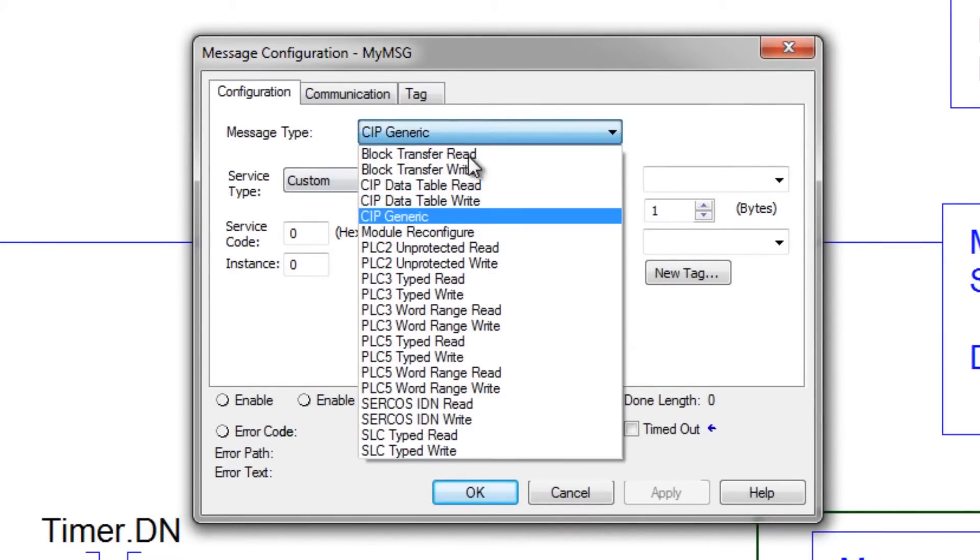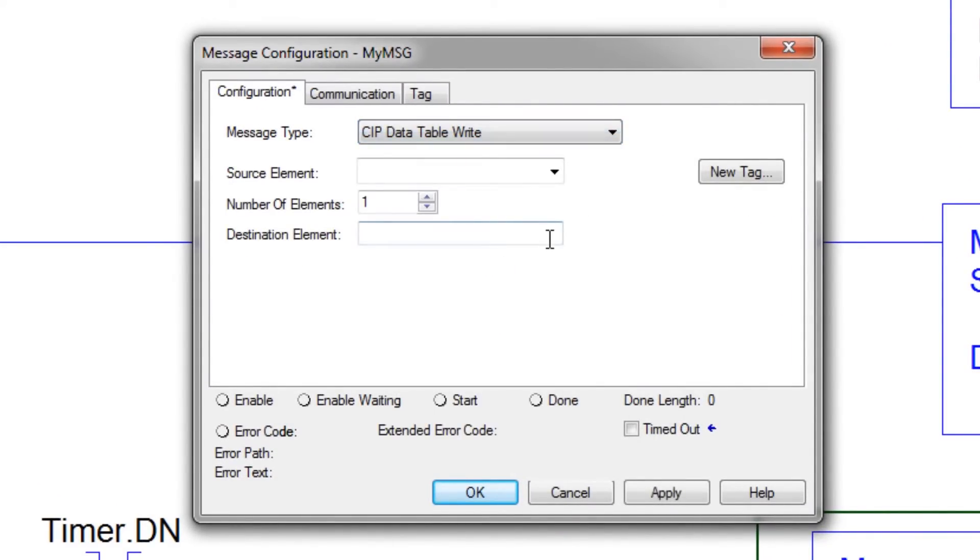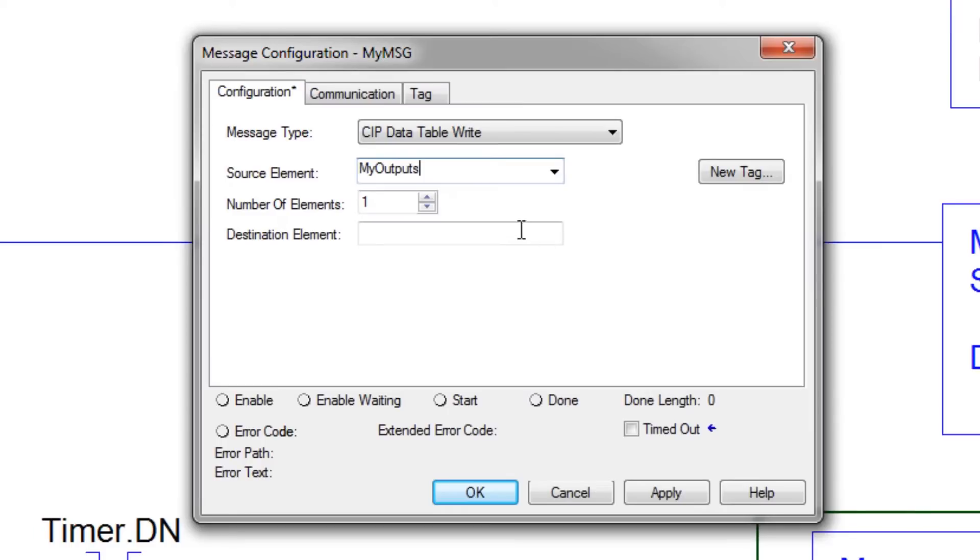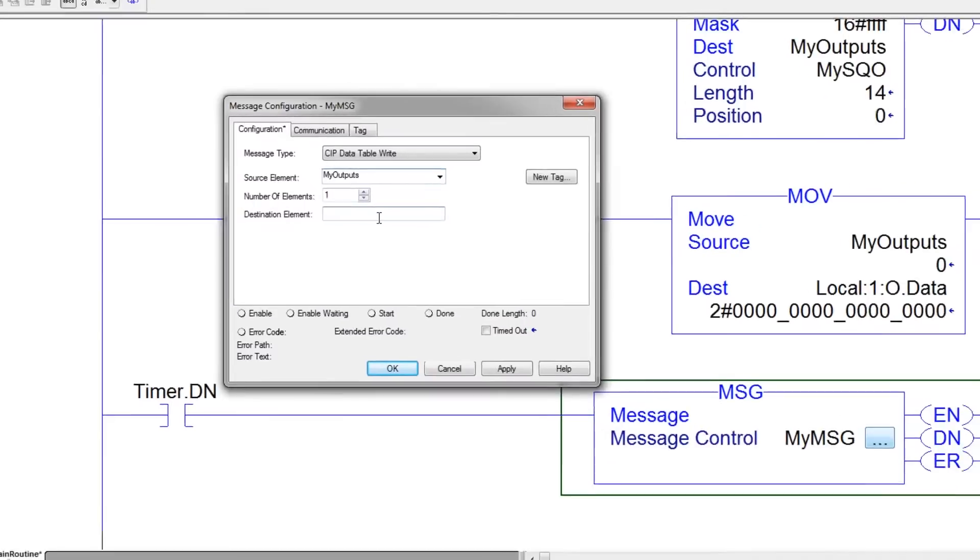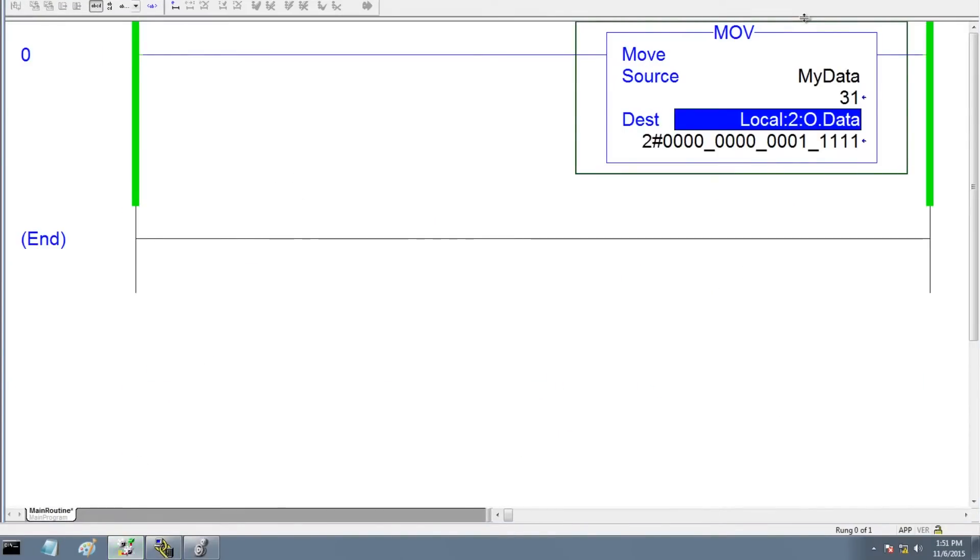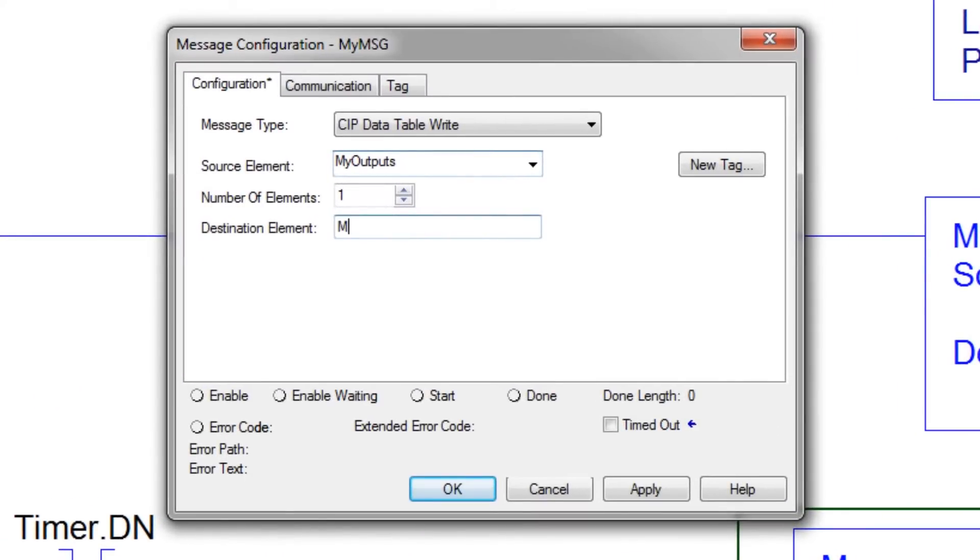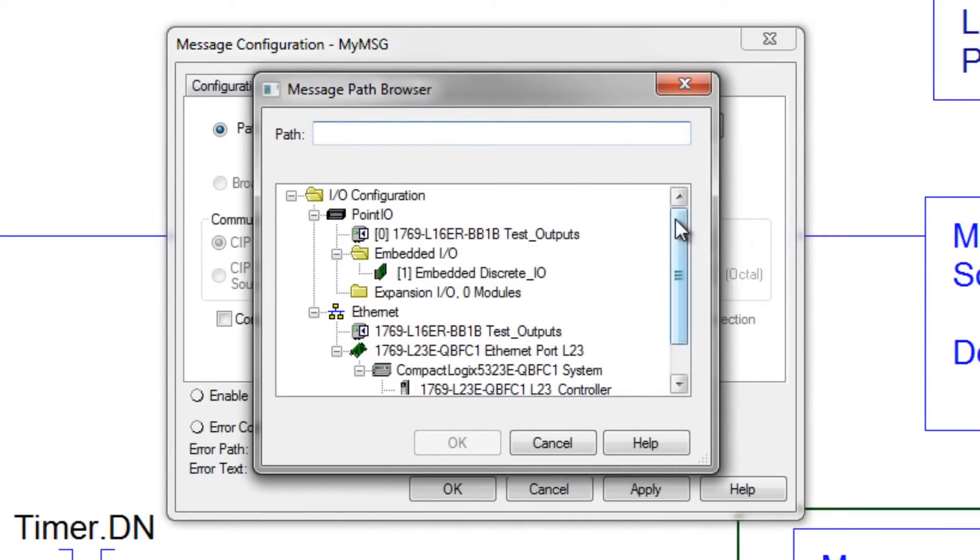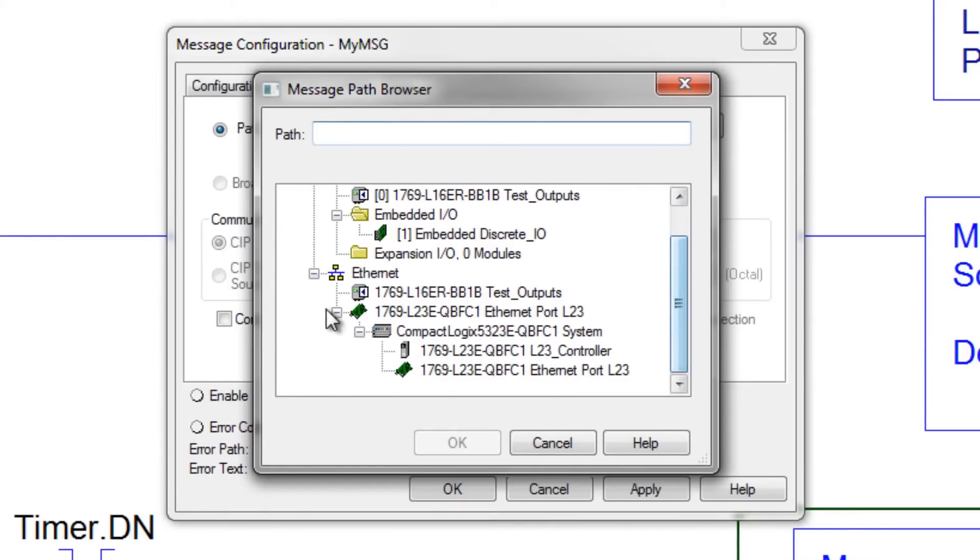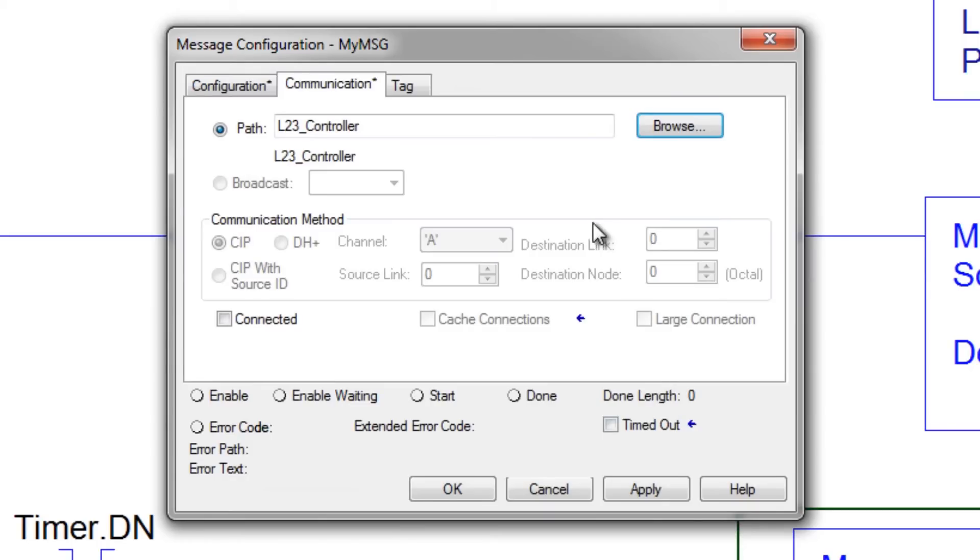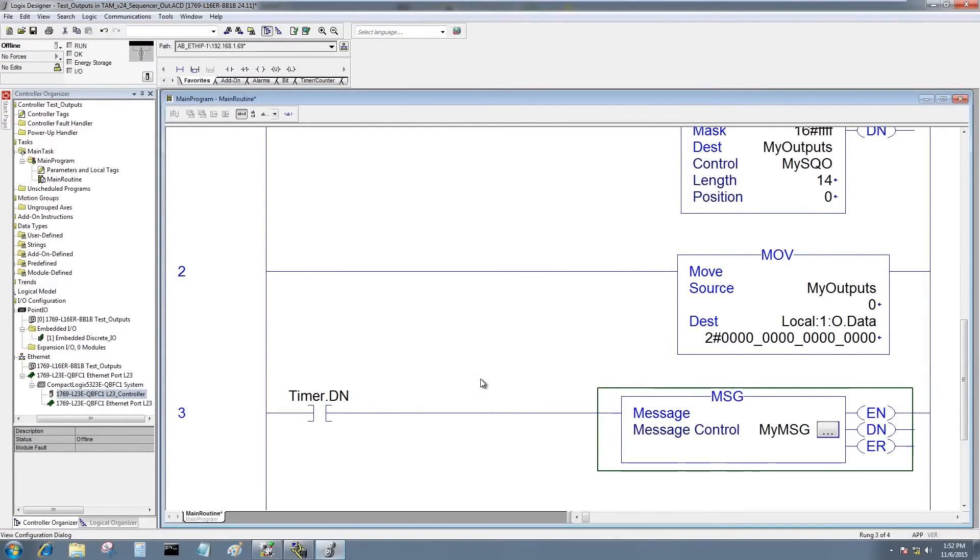Let's go ahead and open the block up. Here I want to do a CIP data write. The source is going to be my outputs. That's the value that's changing in the current program. And the destination will be, if we remember if we go back and look at the L23 it was called my data. So the destination will be my data. Now for communications I'm going to choose the L23 I added to the tree. I want to make sure I choose the controller. And at this point I think I'm all set. I'm going to hit OK.